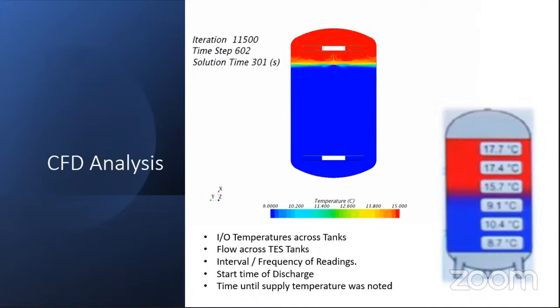See, increasing the delta T is definitely of great help as far as the energy efficiency is concerned. That will also reduce your tank flow, and it will also reduce your pump flow, and it will reduce your storage volume when it comes to a stratified thermal storage tank. It will reduce your volume in the proportion in which you have raised your delta T. So it is of great importance. It is a wonderful way of optimizing your thermal storage tank size. Yeah, that is my answer.